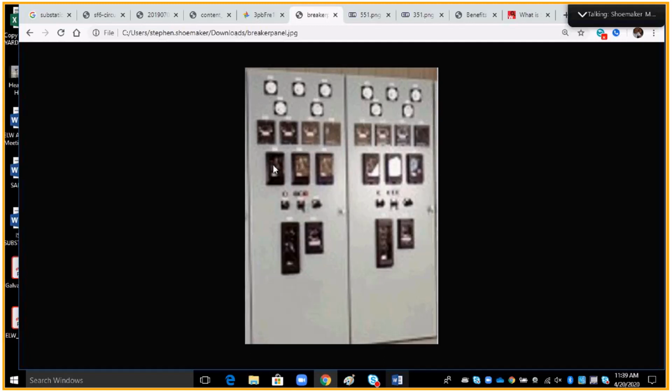First instantaneous, then timed. Now I can go as many different routes as I want to. I can have an instantaneous one time. I can have an instantaneous 100 times. It depends on what you want to do as far as your circuit is concerned. The typical and most used one out there in the world is instantaneous open, 2 timed. After it has completed all of its operations, the reclosing relay will go to lockout.